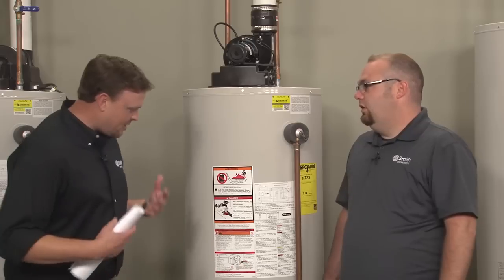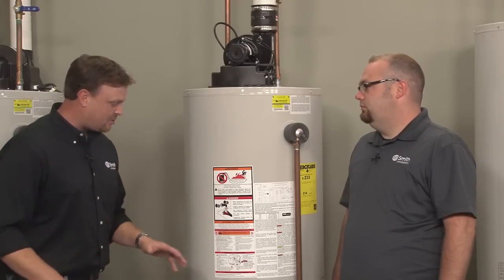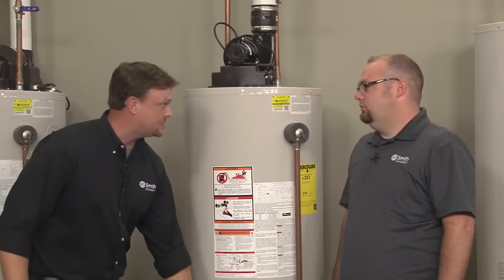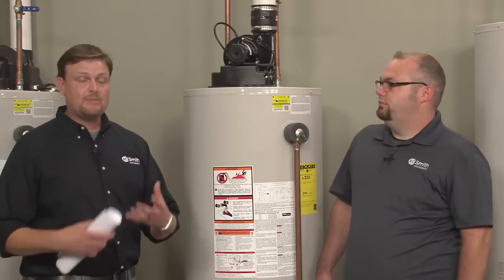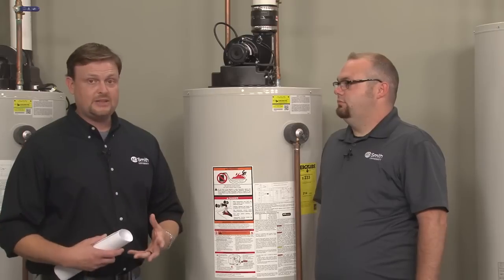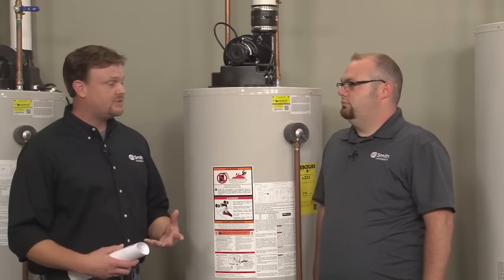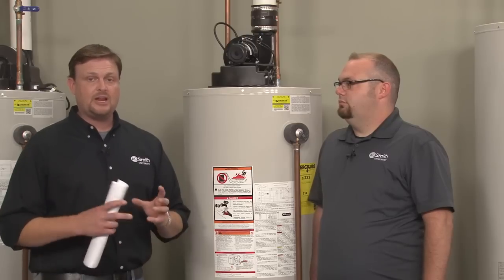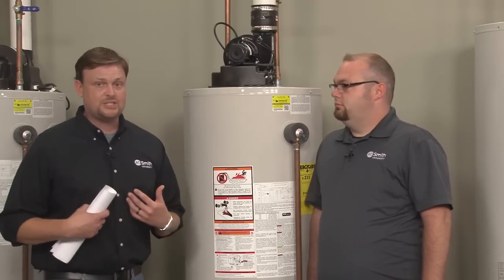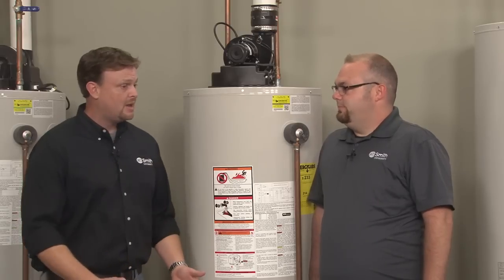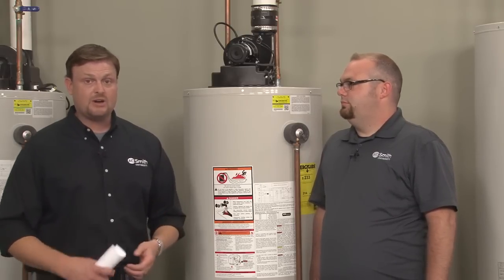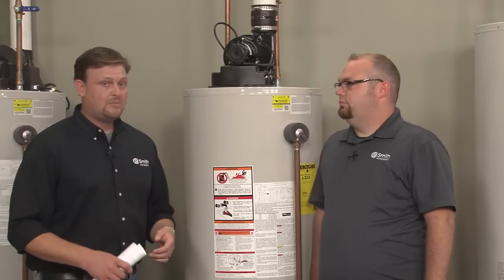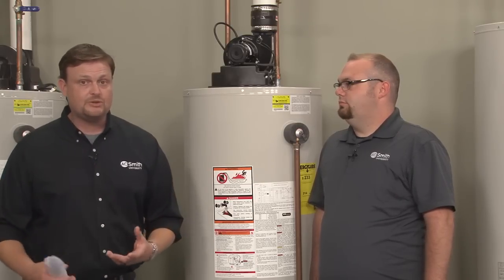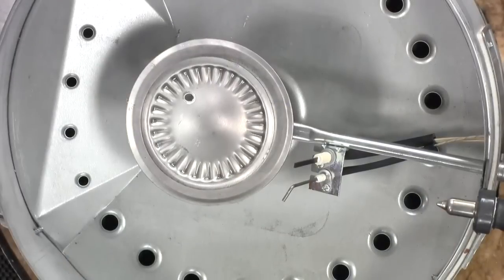All right, so on a 6.1 error code on this unit, I'm going to come up to it, turn it off, turn it back on. I'm going to look through the sight glass. Correct. I'm going to see that glow. I want to see the igniter warm up. It's going to warm up for 17 seconds. If I see a flame and then it goes out, I know that I'm not sensing flame. So I'm going to go ahead and pull my flame sensor out, polish that up, and put it back in there. If there's damage to it, you can go ahead and replace it. And because it is separately replaceable, I don't have to replace the igniter as well. I can replace just the flame rod.